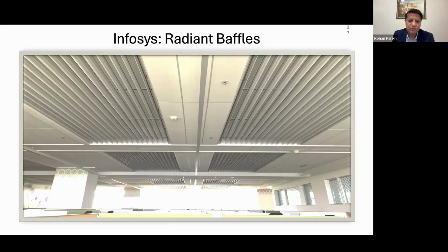It's not a chilled beam. The fresh air that comes in gets dehumidified before it enters, and that air is what's needed to take away the moisture that people introduce through talking and breathing. That's the only moisture entering the room, and it needs to be removed through the dehumidified fresh air that is introduced.